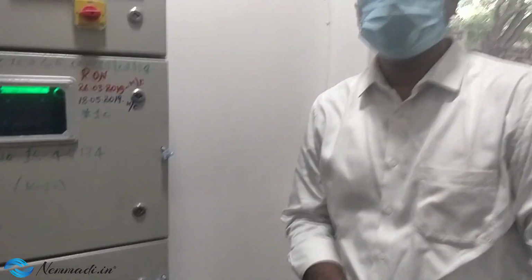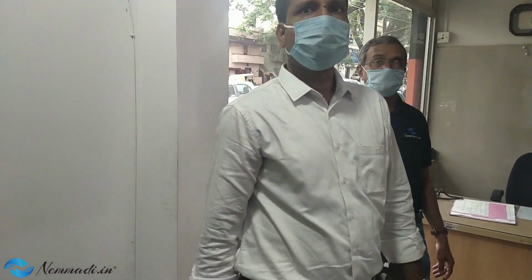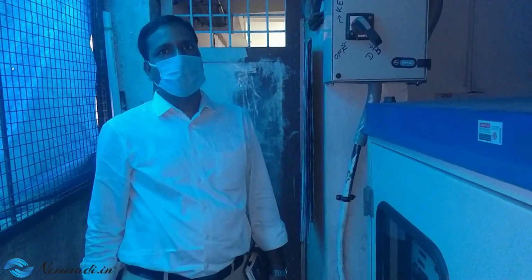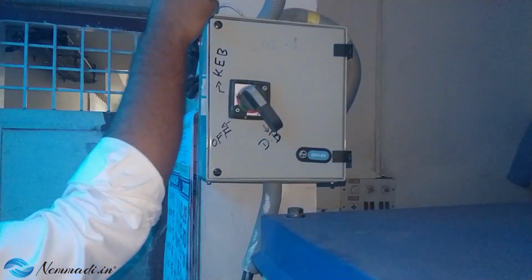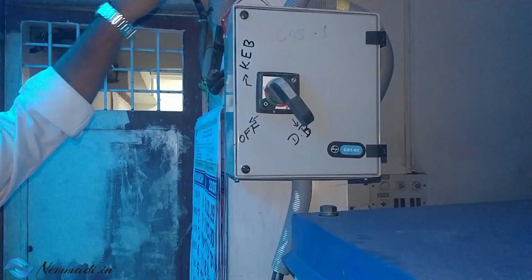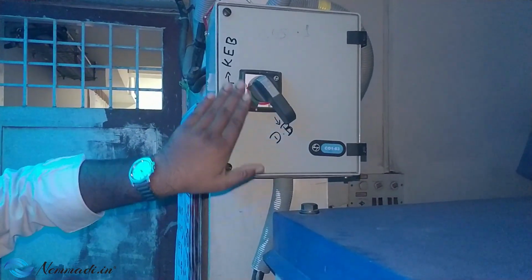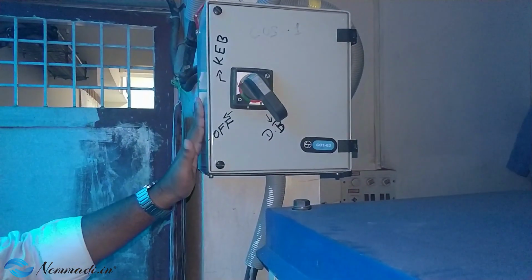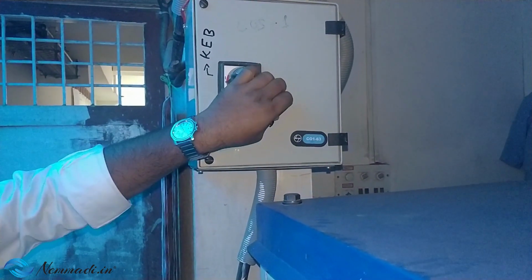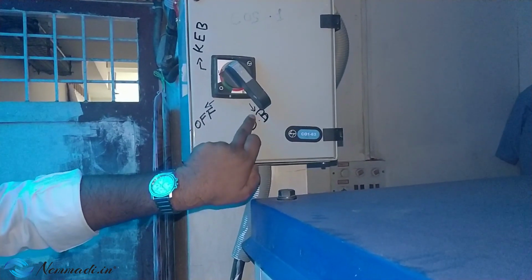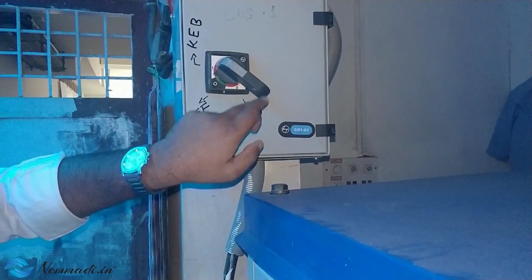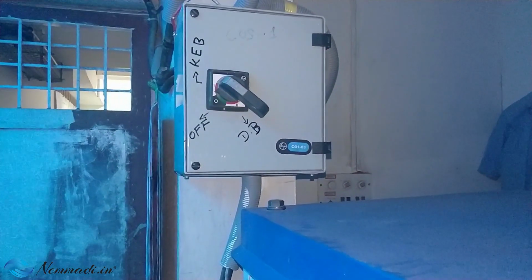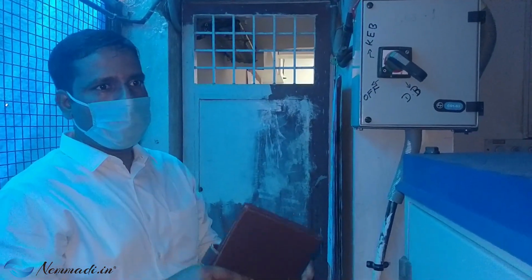Fantastic. Now, can you also take us through the diesel generator? Yes. So we can see this is a changeover switch board. Here we have the electricity board power supply connected to this board, and whenever there is a failure in the power supply, you can manually switch on this MCB changeover switch to the DG side. When it is switched to the DG side, DG power will be connected to your distribution board, and from there we will get the DG supply. So this is done manually.